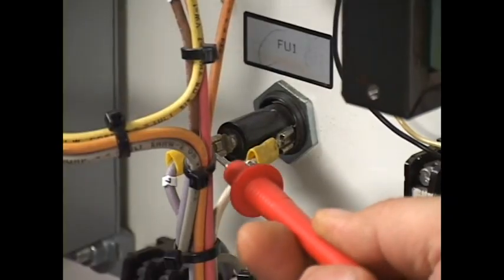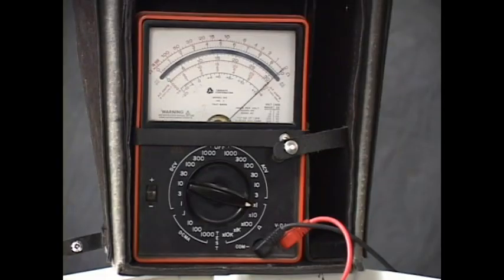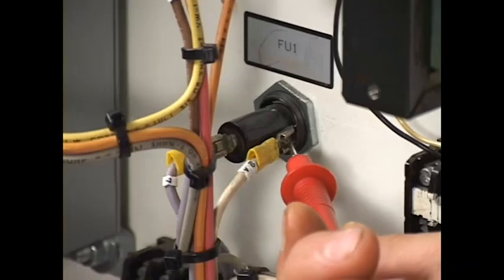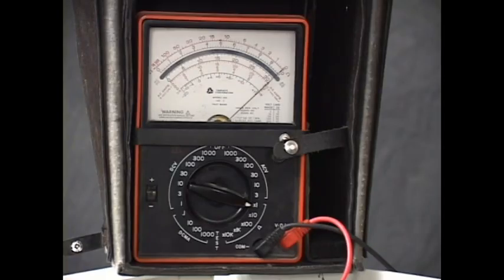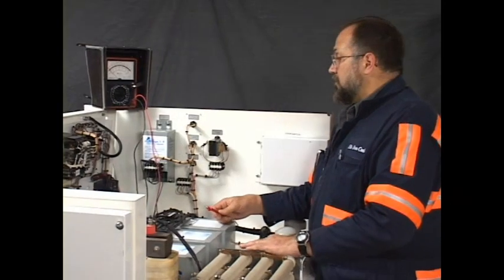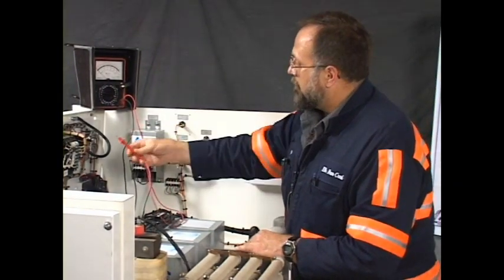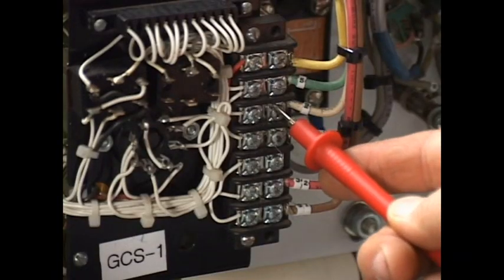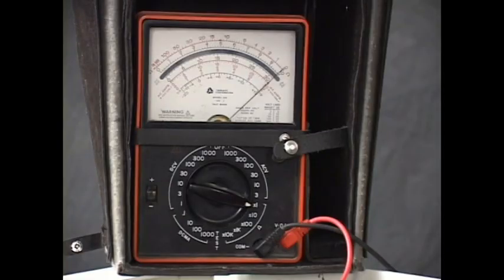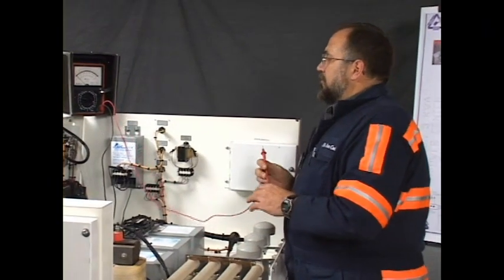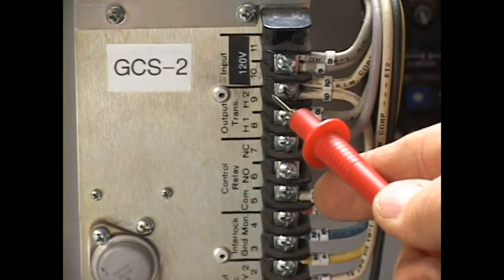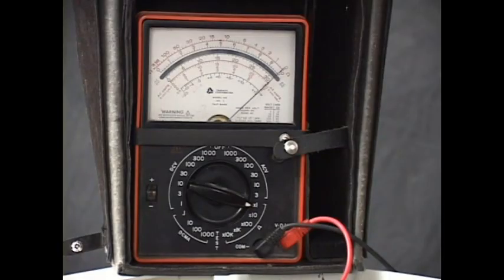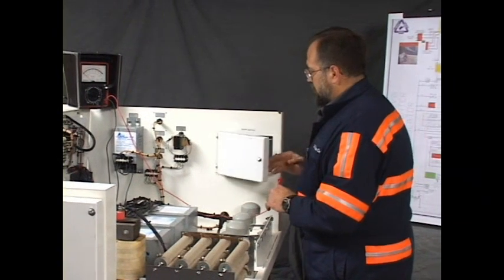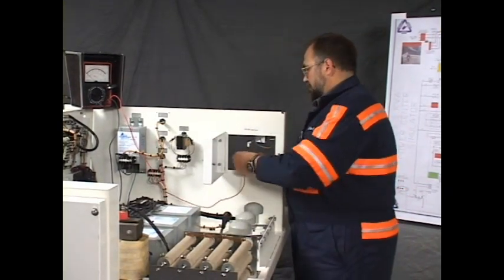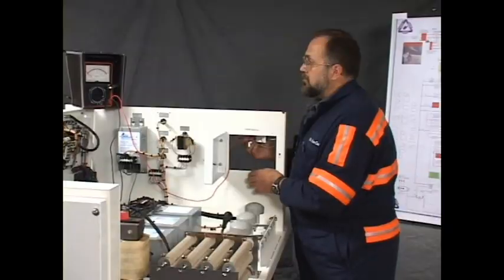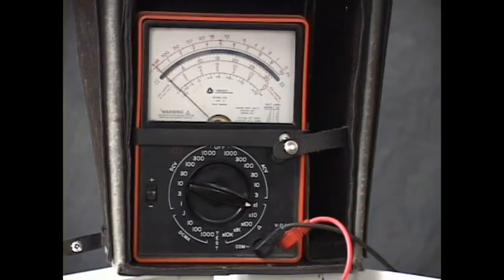And we have continuity. From there to the line side of the fuse holder, we have continuity. Through the fuse to the load side of the fuse, FU1, we have continuity. There the wire number changes to 9. From 9 on the fuse holder, the first point we can reach is 9 on GCS1, wire 9 on terminal 1. And from there we go to wire 9 on GCS2. We still show continuity. And we're going to go to the door switch. It's the next point in the line. Wire 9 on the door switch. That's an open circuit. There's no continuity.